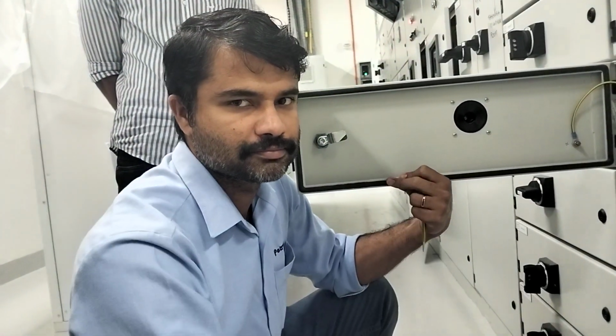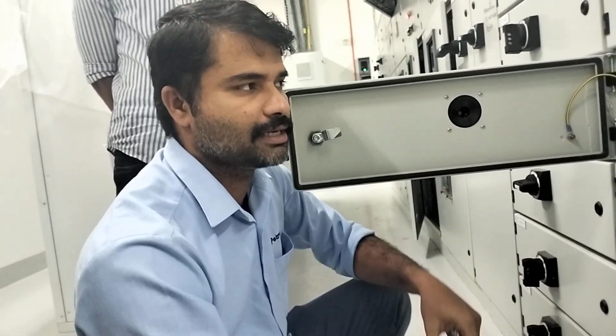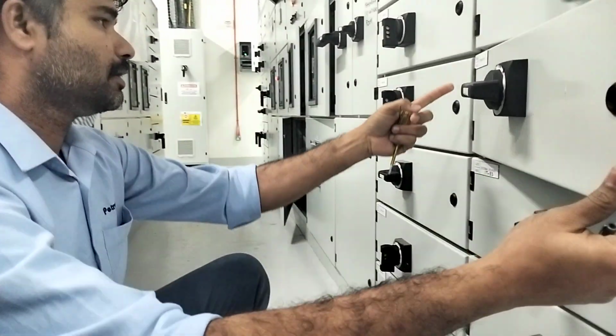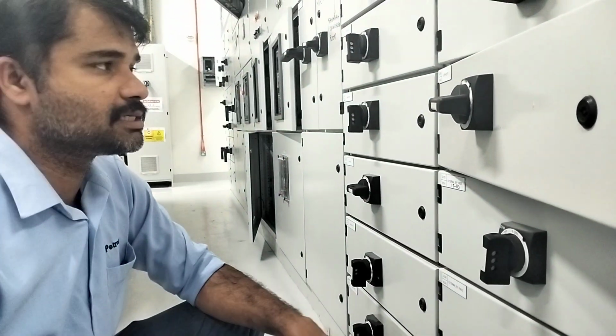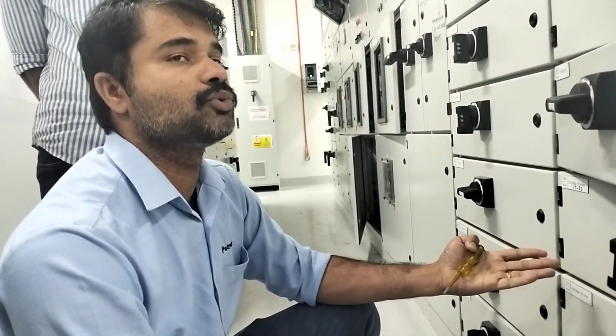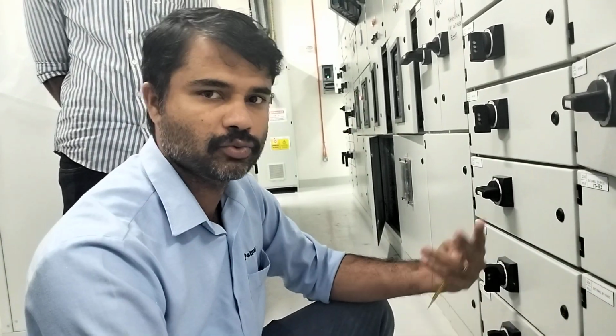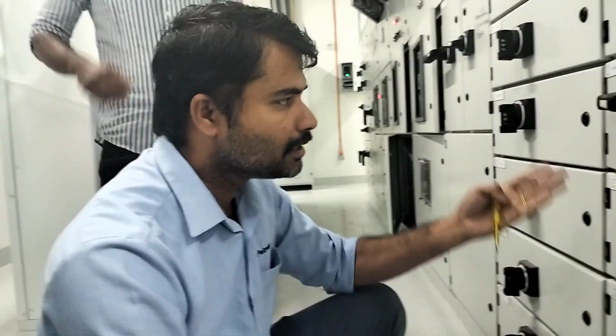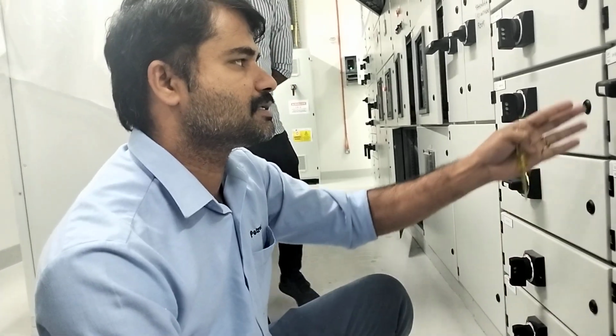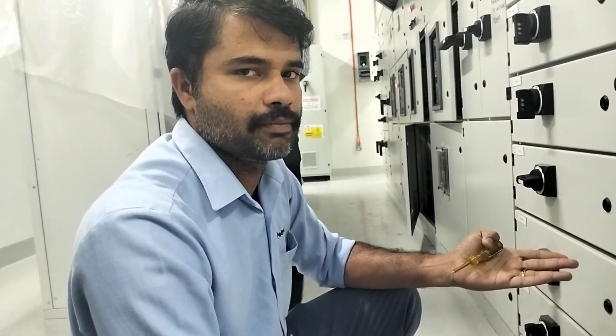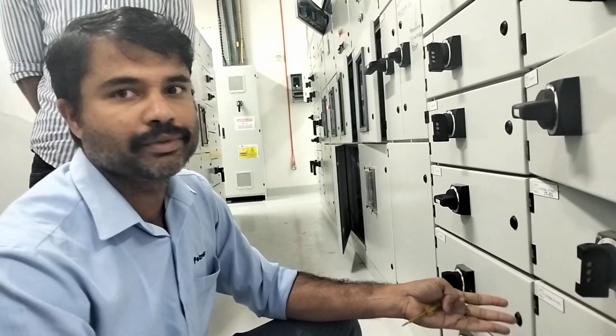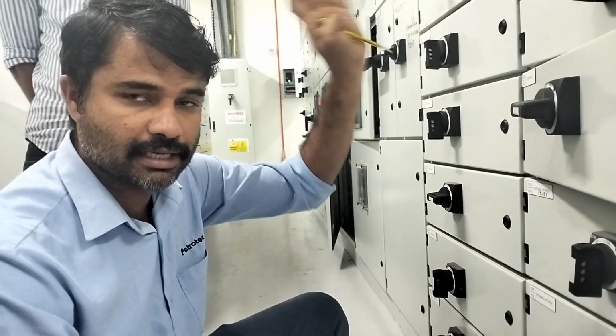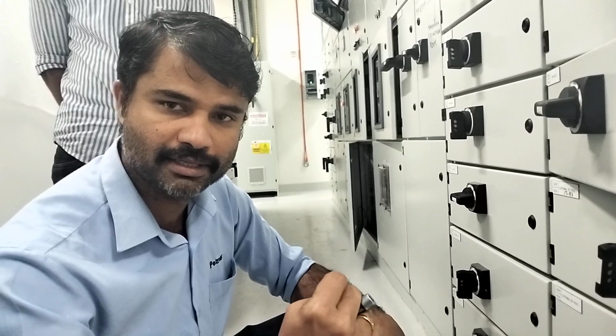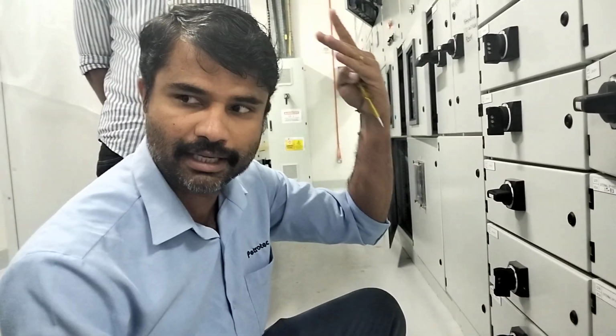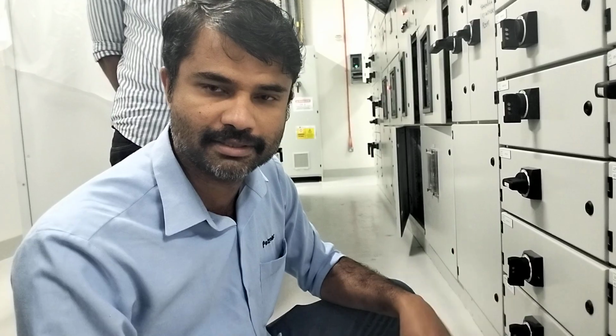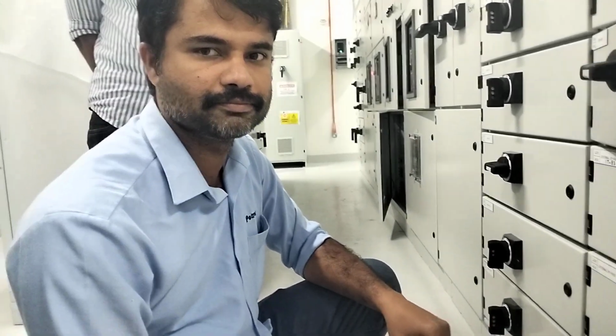Like ELCB. Let's say this is an 80 ampere breaker. Okay, 160 ampere breaker, you are setting it full. Let's say it's taking maybe 200 ampere. It will trip maybe after one day or 2 days, 3 days. If it is taking 3 times or 4 times the current, let's say 300 or 400 ampere, it will trip maybe after 1 minute, 2 minutes, 3 minutes. If it is taking 1000 ampere, it will take maybe 150 millisecond, 200 millisecond. If it is taking 10,000 ampere with short circuit, it will trip in 20 milliseconds, 30 milliseconds. Okay. Got it.